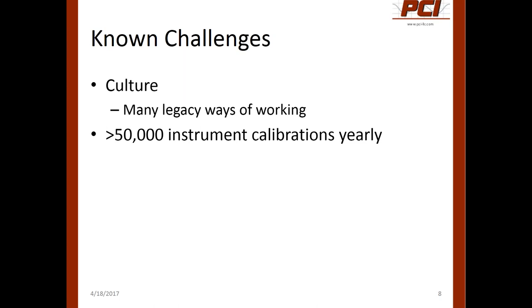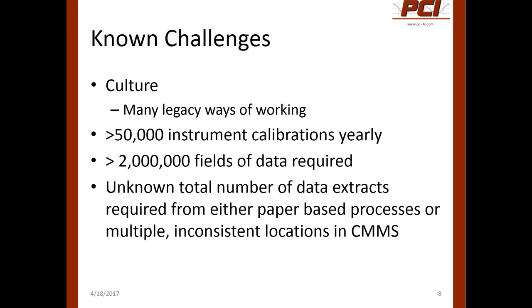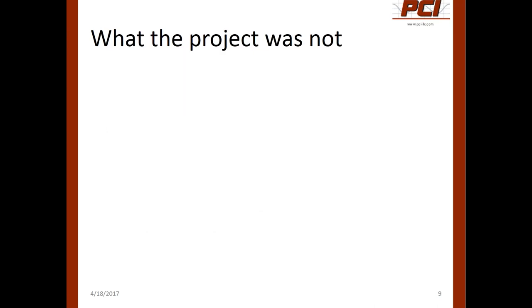There were over 50,000 instrument calibrations done on a yearly basis total. We knew we had over 2 million fields of data that needed to be developed for this project. We had an unknown total number of data extracts required from either paper-based processes or multiple inconsistent locations in the CMMS systems. For example, a text field utilized within the CMMS system to capture test points was used inconsistently, so we couldn't develop a data migration to get the data out. We had to define where things would be manually readied, and where we could potentially extract data through data migration protocols.